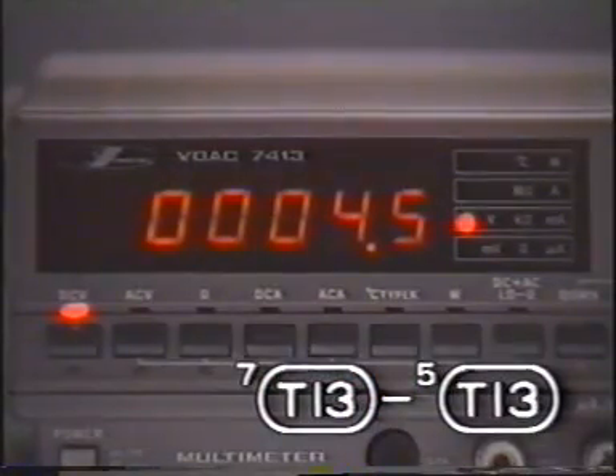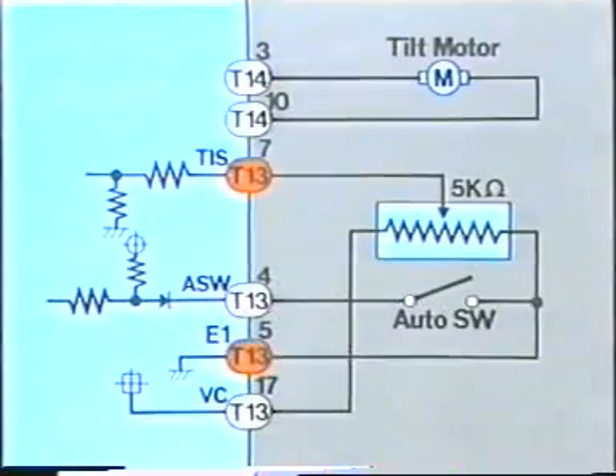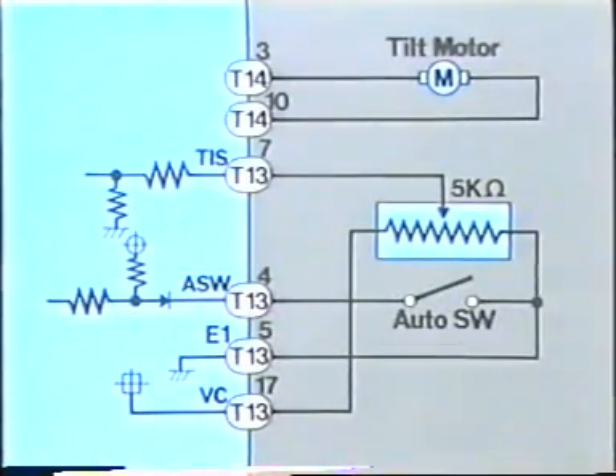Normally, the voltage should be between 0.8 and 4.2 volts, but the meter reads 4.5 volts. The voltage being higher than 4.2 volts suggests an open in the circuit somewhere between the sensor and terminal E1. You can narrow the problem down further by turning the auto switch on and testing the voltage between output terminal ASW4T13 and input terminal E15T13.